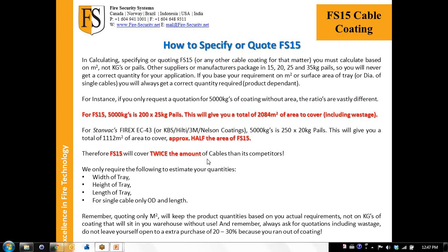Otherwise it becomes difficult. You can't work it out on a tray calculation. You would have to work it out on an OD, or a pi. So if you have 5 cables in a cable bundle, you take basically 5 times the OD and calculate the area. Yeah, that's exactly what we would do. All we're really doing is taking the 100 mil OD, times 3.14, which is pi, then times the length, and there's your square meter rate.